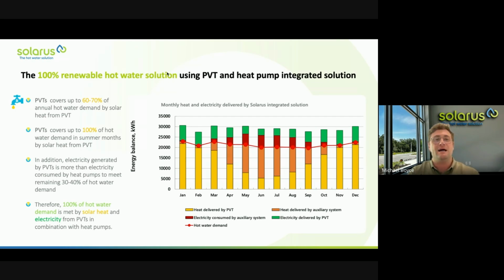We generally size the system for the thermal or PVT to meet between 60 and 70% of the annual hot water demand using solar thermal. If we sized it the opposite way around to meet 100% of the hot water demand in winter, the system would be extremely oversized for summer, which would then cause stagnation, and the system would not be able to perform. So I'm just going to break down this first point.